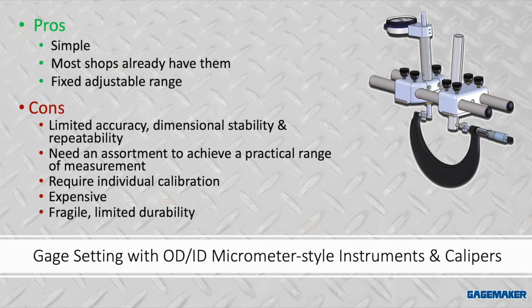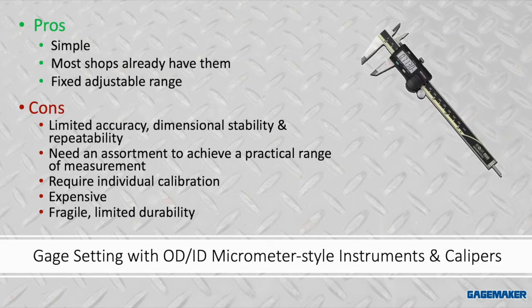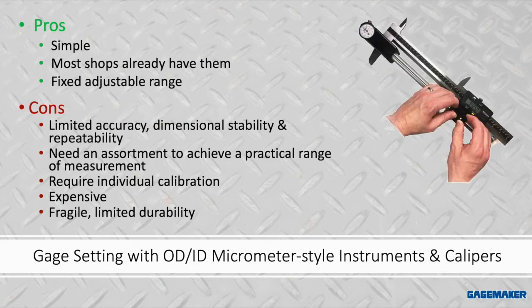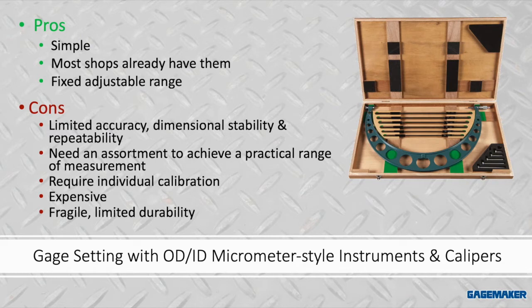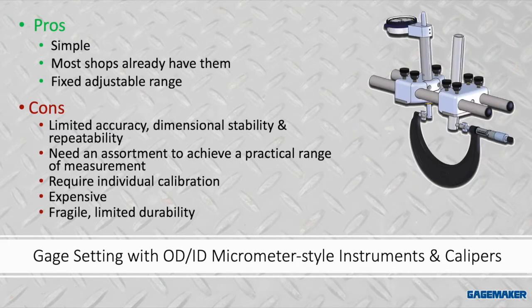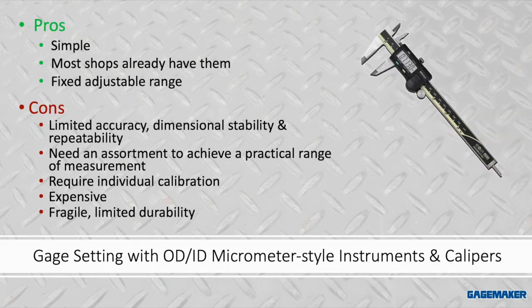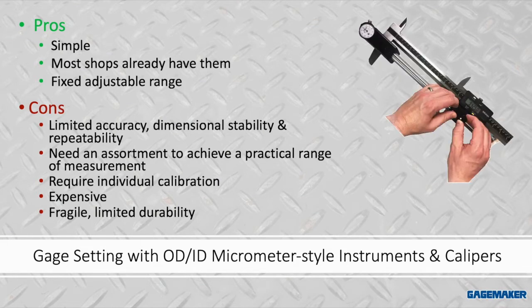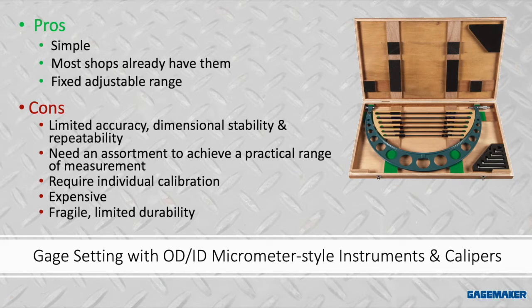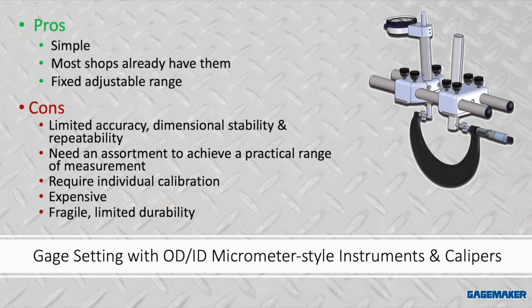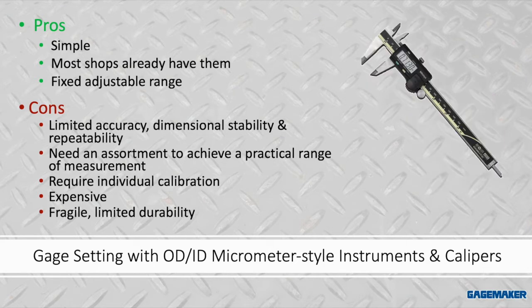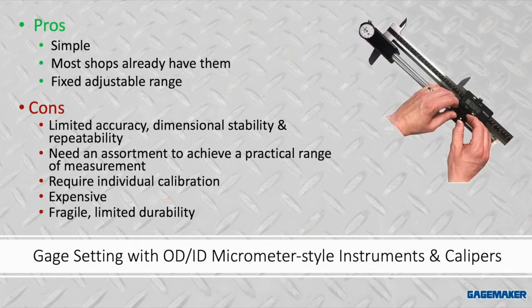Now let's take it a step further and compare to micrometer-style gauges. So every machine shop has a set of OD and ID mics. This is a very common practice to measure product with them and set gauges with micrometer-style instruments. However, doing so can be very cumbersome. It's time-consuming, and now this is where you really start to see a loss in accuracy as opposed to a dedicated setting master or the accuracy you achieve with gauge blocks. In addition, while they're adjustable, that range of adjustability is limited. It's based on the range of the instrument, so you still may need multiple OD and ID mics to achieve the same task that you could with one robust PHMD and some fixtures.